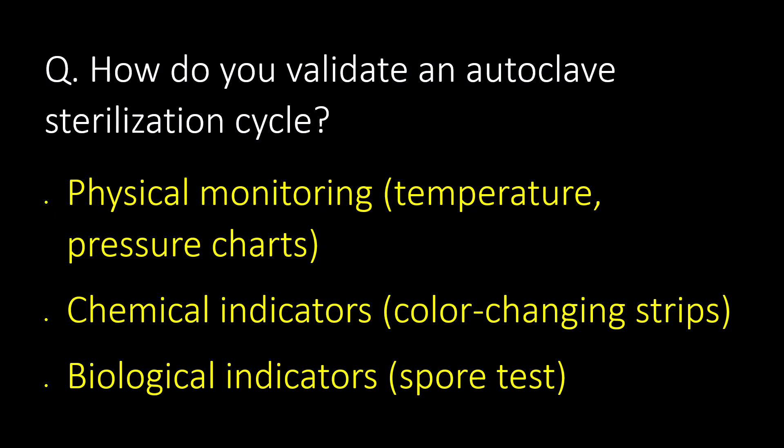How do we validate an autoclave sterilization cycle? First, physical monitoring — that is, temperature and pressure charts. Second, chemical indicators — the color-changing strips. And third, biological indicators, which include a spore test.